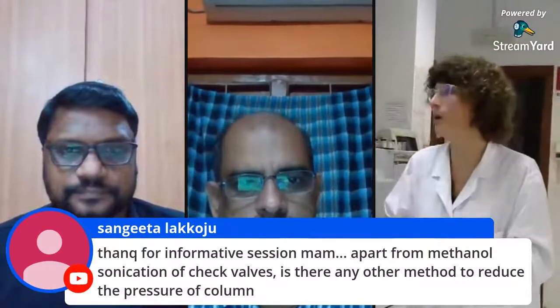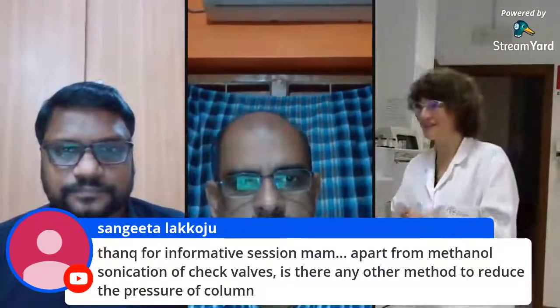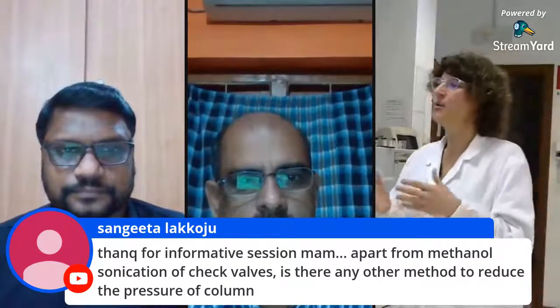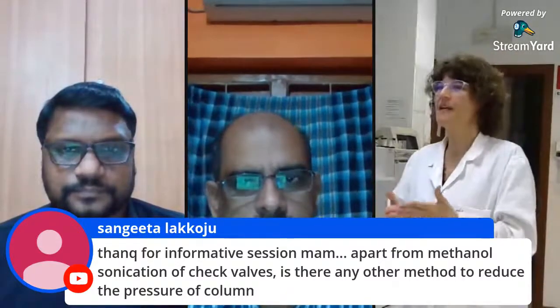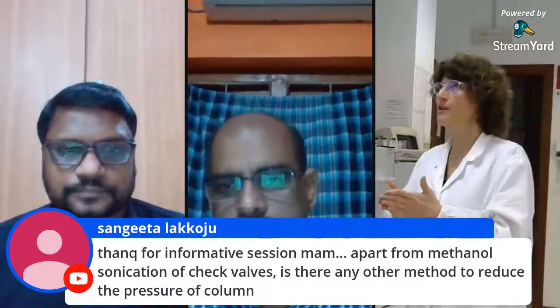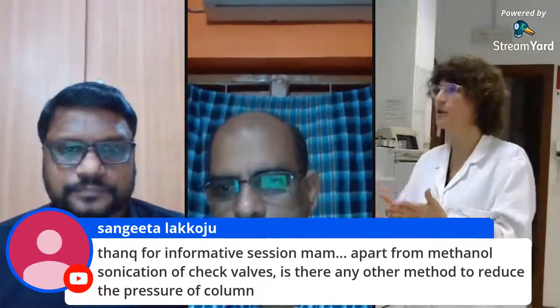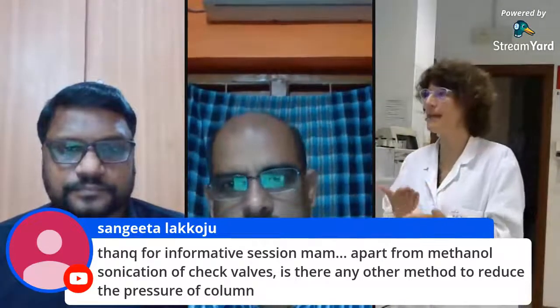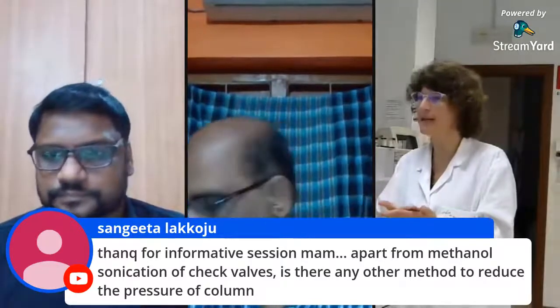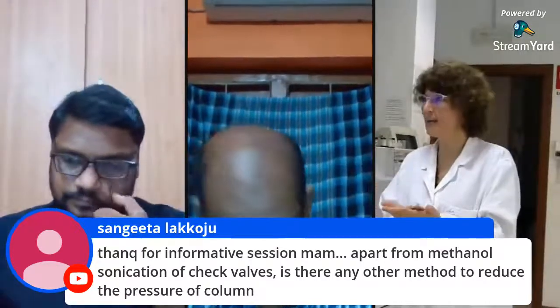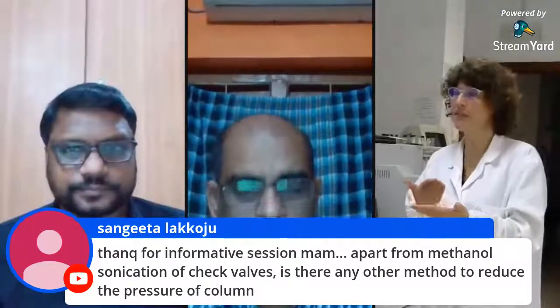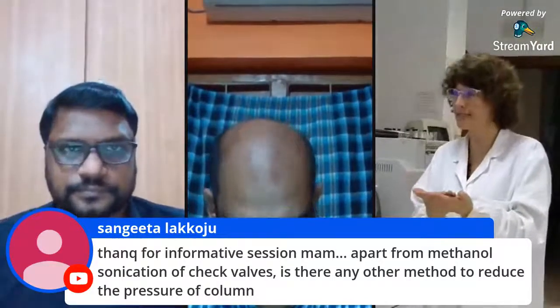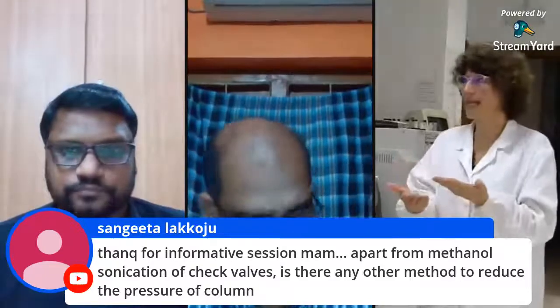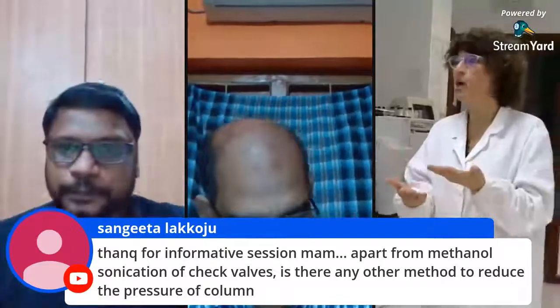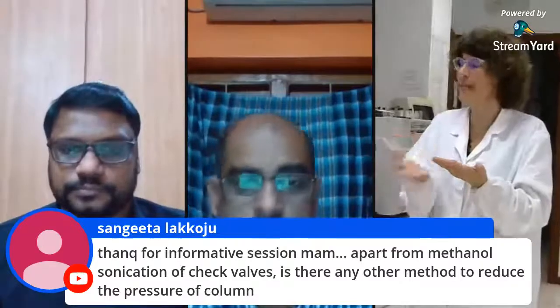To reduce the pressure of the column. Oh, well, this is a good question. Well, you have to use chromatography grade solvents because otherwise particulate matter in the solvents may clog the system. And if you do not filter properly the solvents, day after day, little by little, you will see an increase in the pressure of the system.